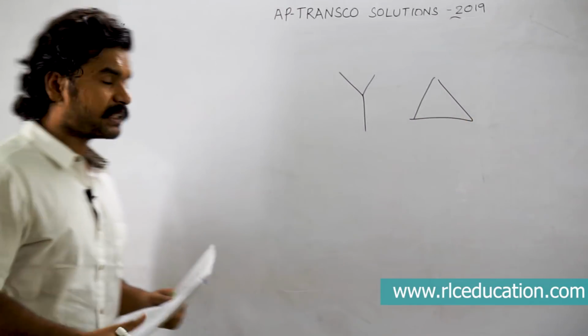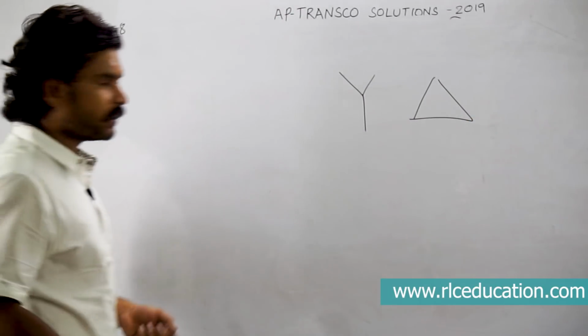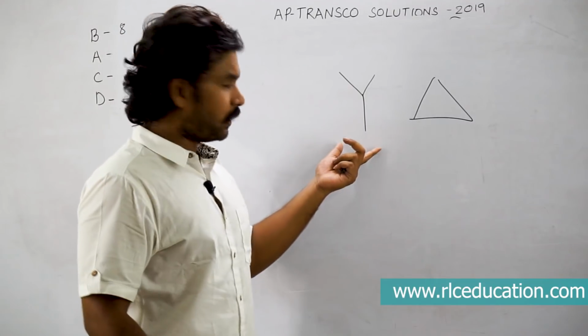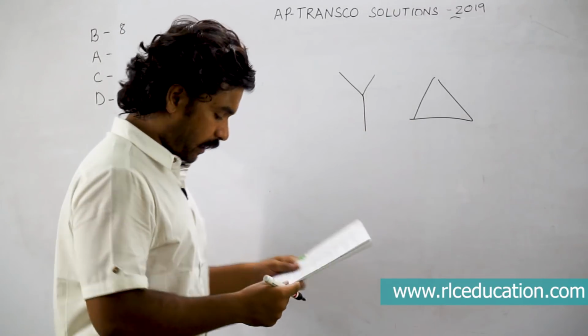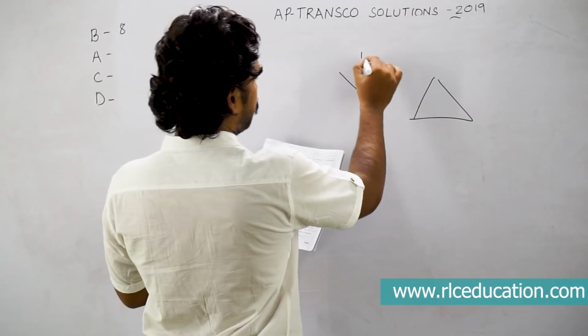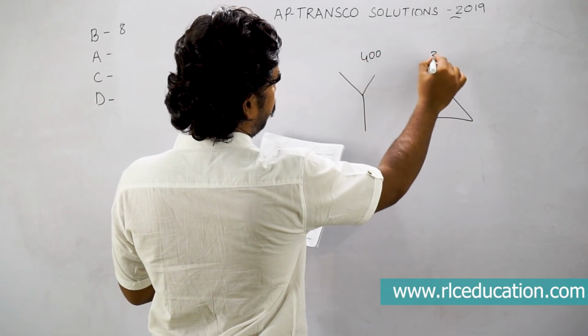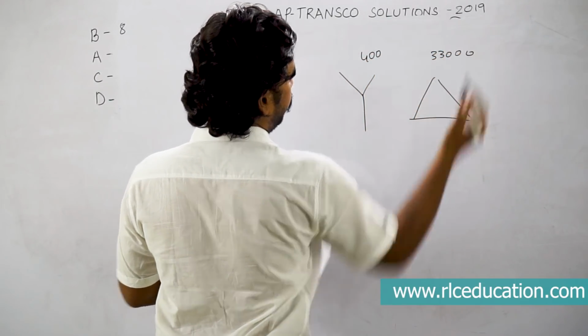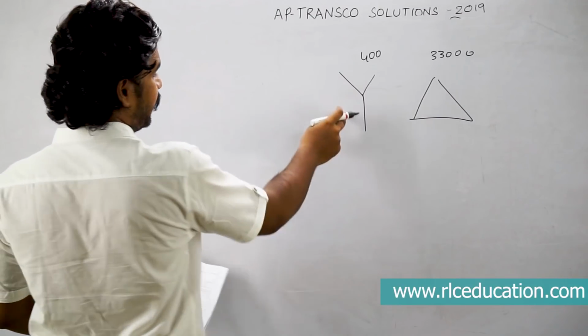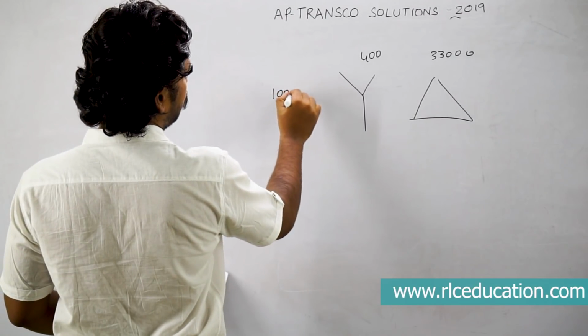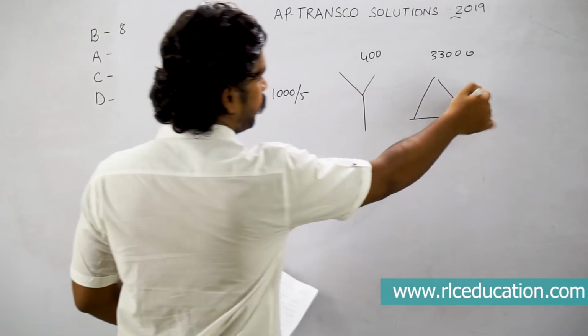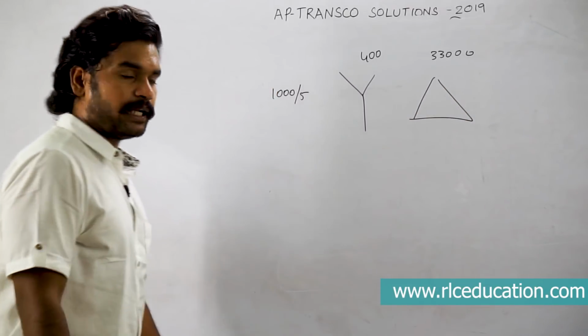So I just want to discuss question number 8 in B set. He says that there is a transformer which is connected in star and delta, and the voltage ratio of this transformer is 400 on the star side and 33,000 on the delta side. He has given you the CT ratio on the star side as 1000 by 5 and is asking you to find out what is the CT ratio on the delta side.